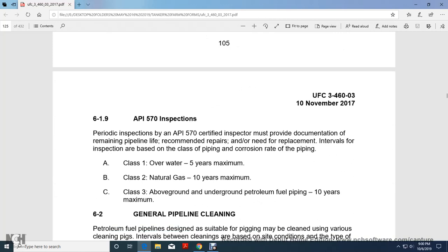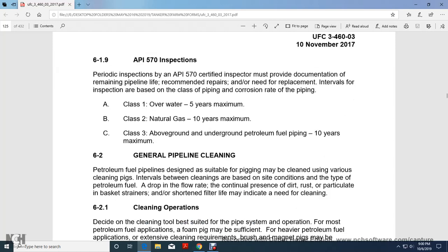619, American Petroleum Institute 570 inspection. Periodic inspection by an American Petroleum Institute 570 certified inspector must provide documentation of the remaining life of the pipeline, with recommended repairs needed and replacement. Intervals of inspection are based on the classing of the pipe and the corrosion rate of the piping. Class 1, over water, 5 years maximum. Class 2, natural gases, 10 years maximum. Class 3, above ground and underground petroleum fuel pipeline, 10 years maximum.